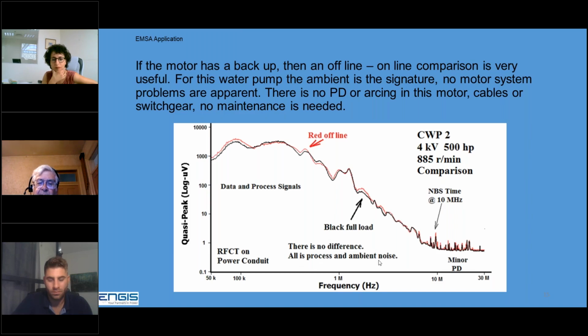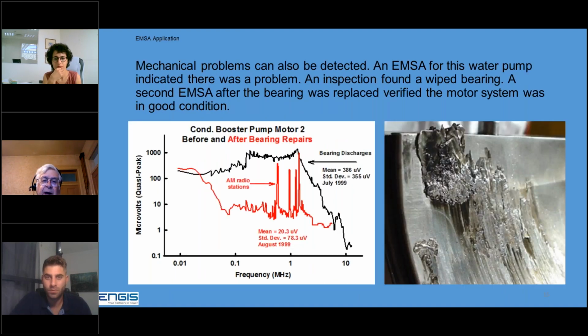All of the signature that we're seeing is the ambient noise at that site. And in fact, what we could pick up in this location is the 10 megahertz National Bureau of Standards time marker at 10 megahertz. So it's a very quiet motor. So there's nothing wrong with the motor, the power cables, the switchgear, the transformer, the bus feeding it. No maintenance is needed. The other motor, by the way, was exactly the same.